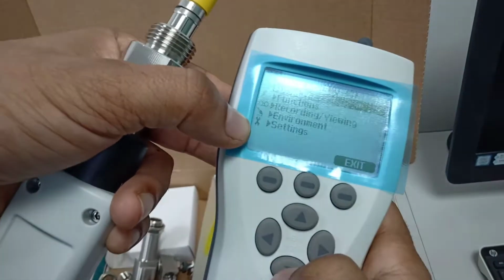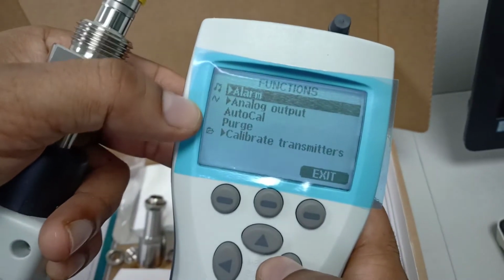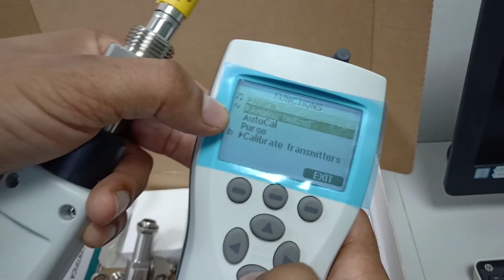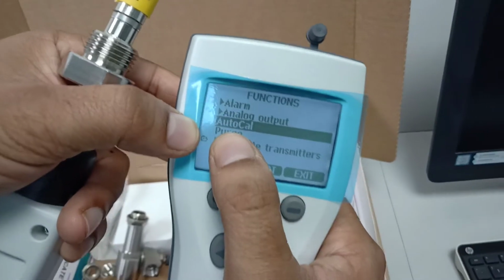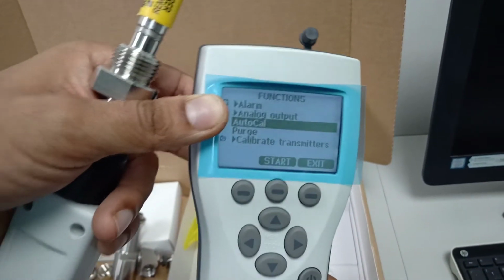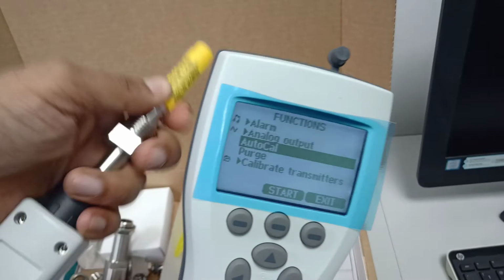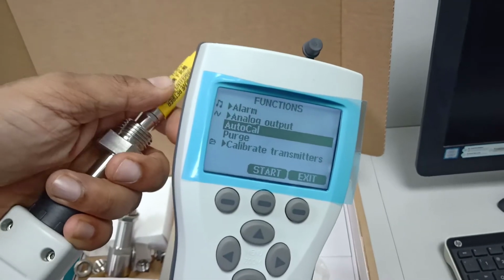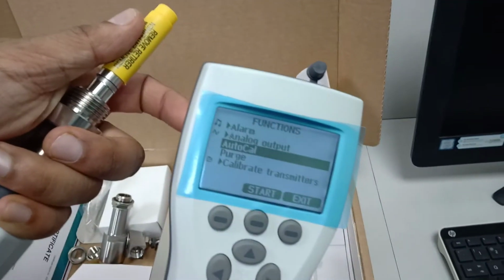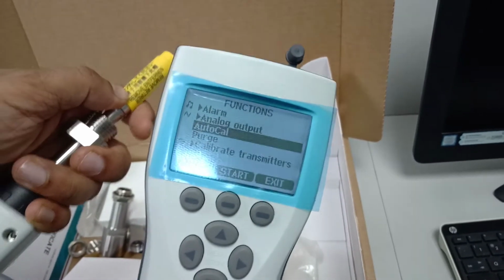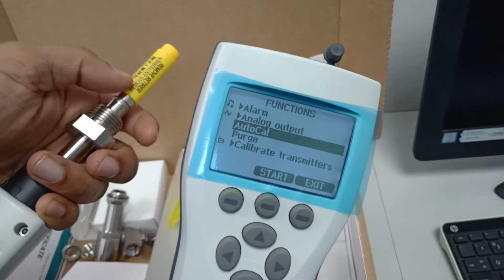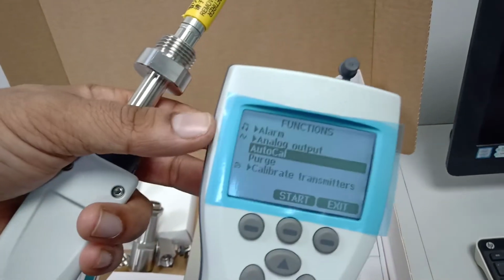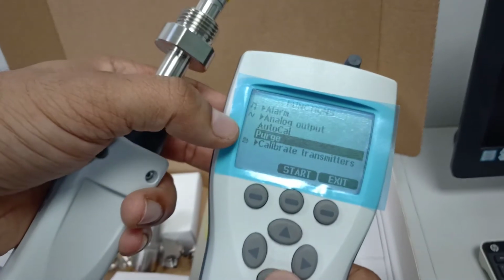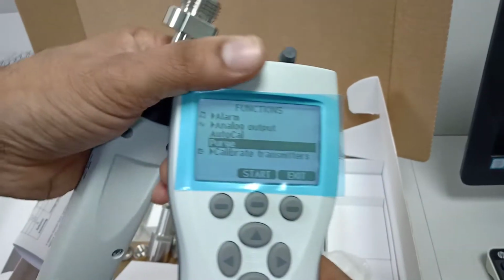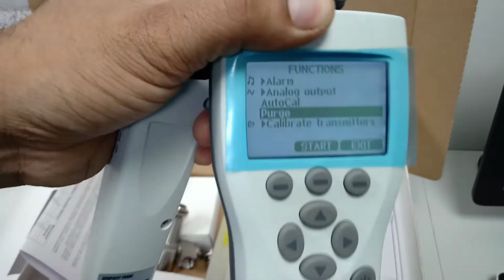And moreover, you have other functions as well. You can set the alarm, you can get the analog output. This is auto calibration. So auto calibration is performed whenever there is excess humidity to remove the moisture. So what happens is, as the moisture removes, it draws a curve between relative humidity and 1/T. So relative humidity is inversely proportional to temperature. So it draws a linear graph between RH and 1/T. You can purge. So purging is automatic when you put it in the dry conditions. So it takes 5 minutes to purge.